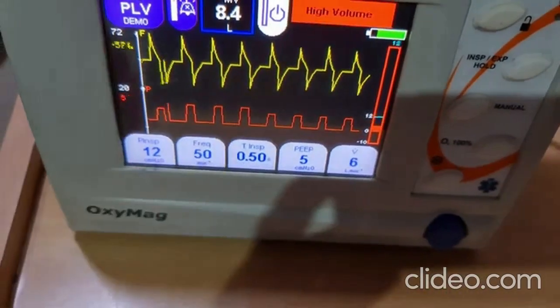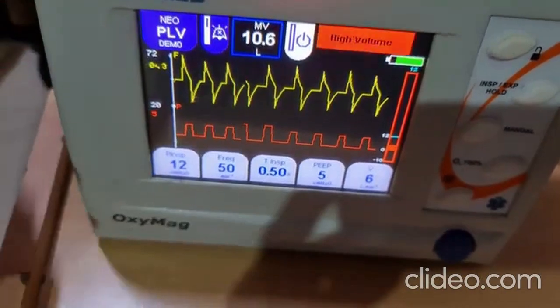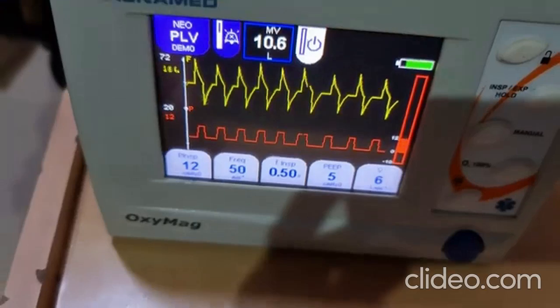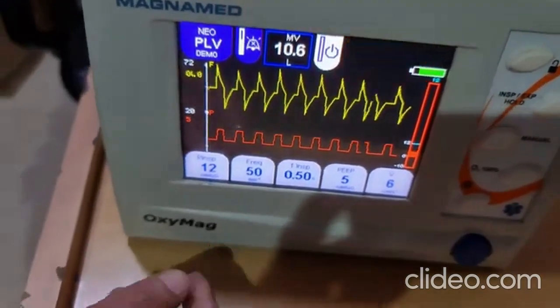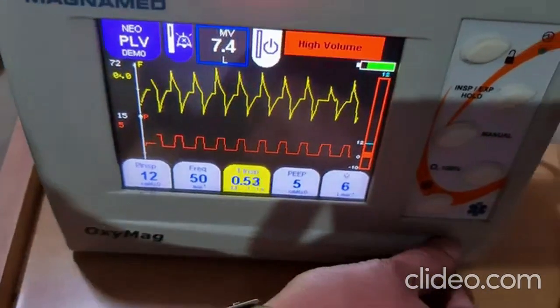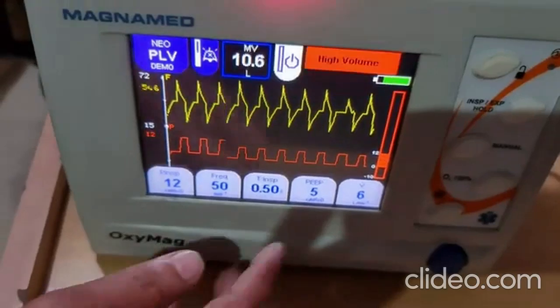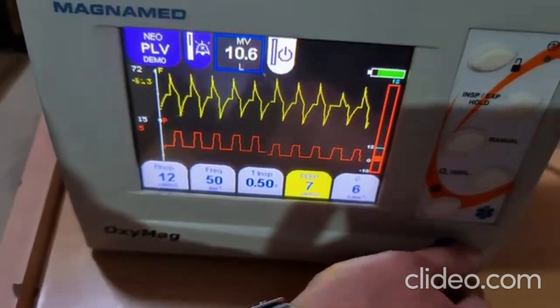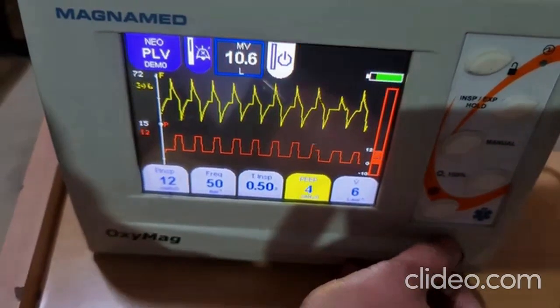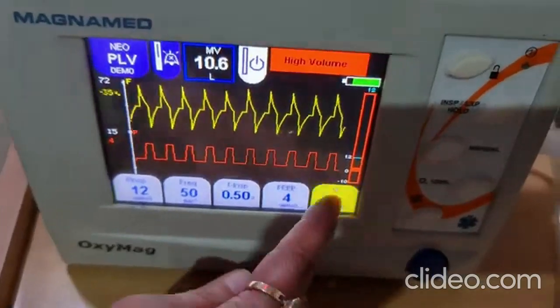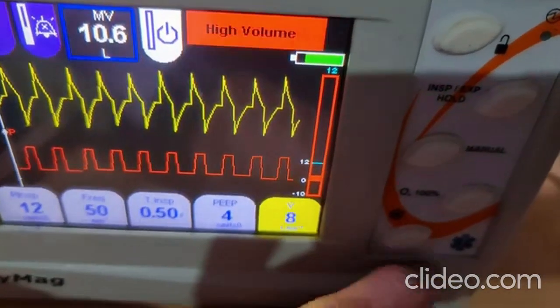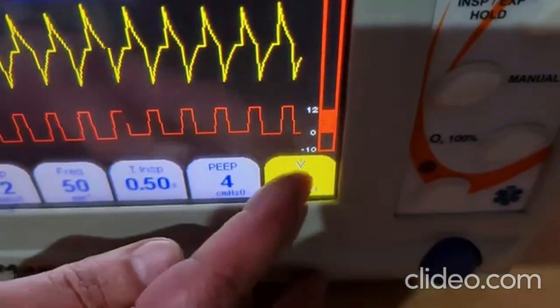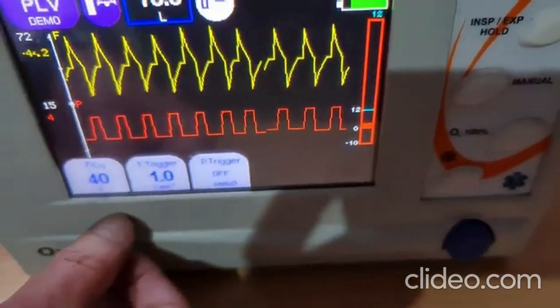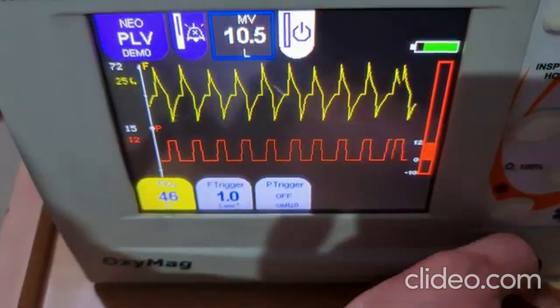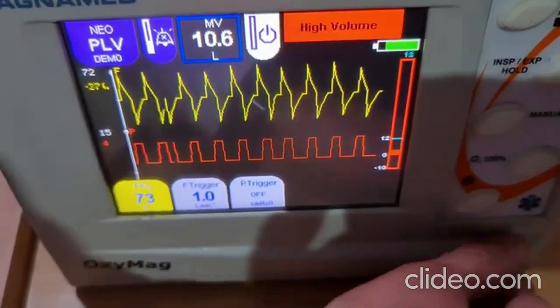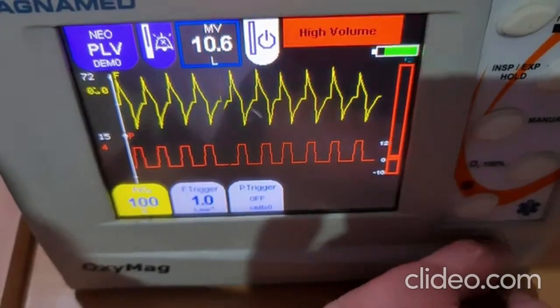See, this is confirm. If you will not confirm, it will come to original settings, the previous settings. This is inspiratory time, confirm. This is PEEP. Very simple to use. This is the flow, can increase decrease flow also. Confirm. You press this, the next page will come. Here you can adjust the FiO2. FiO2 you can adjust this from 35 to 100%.